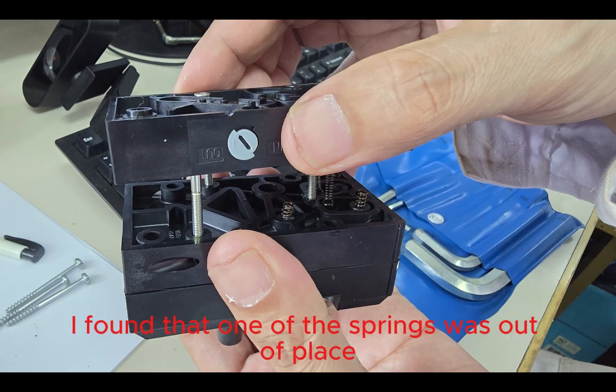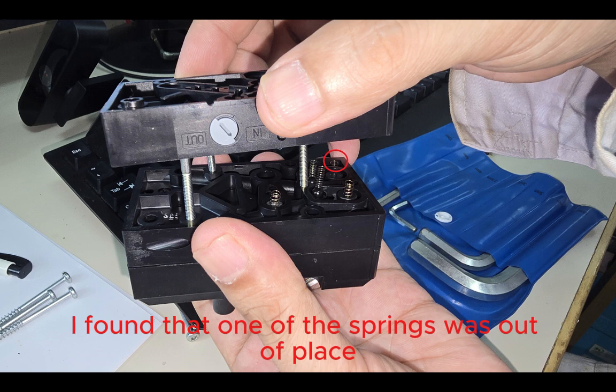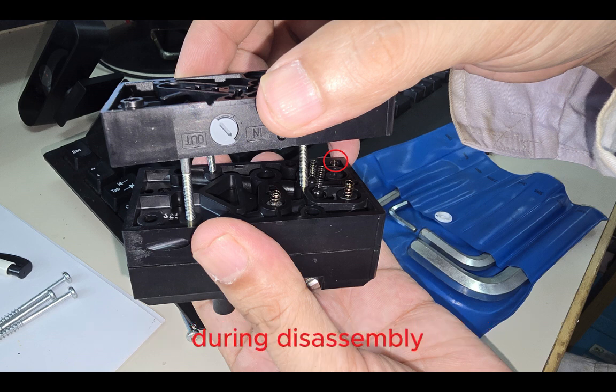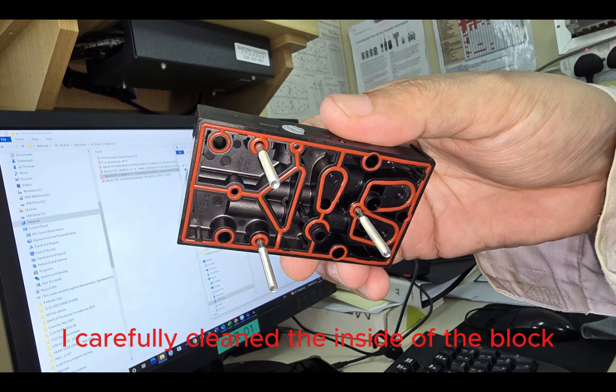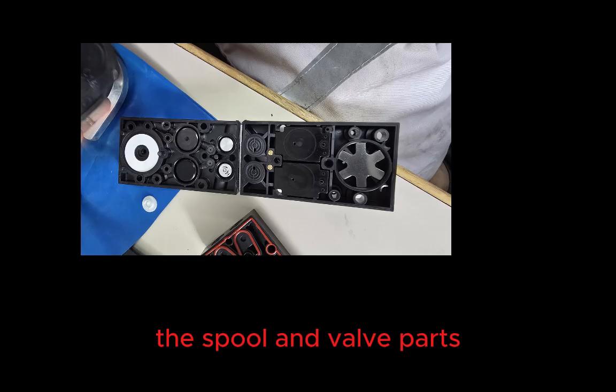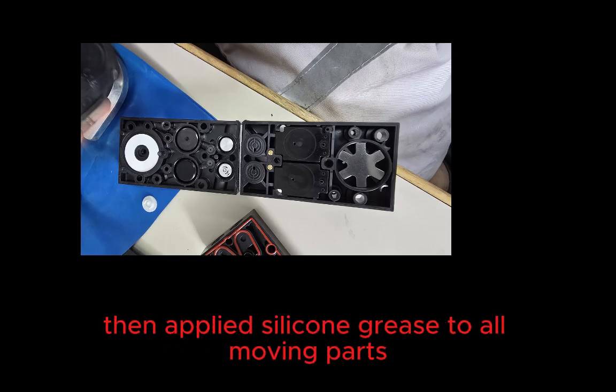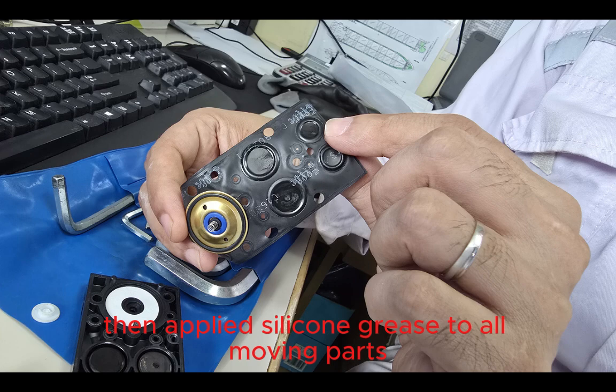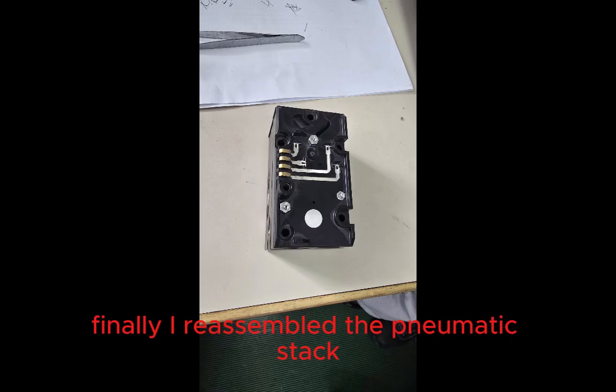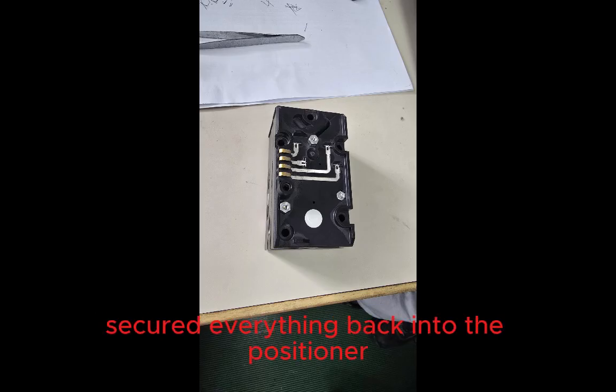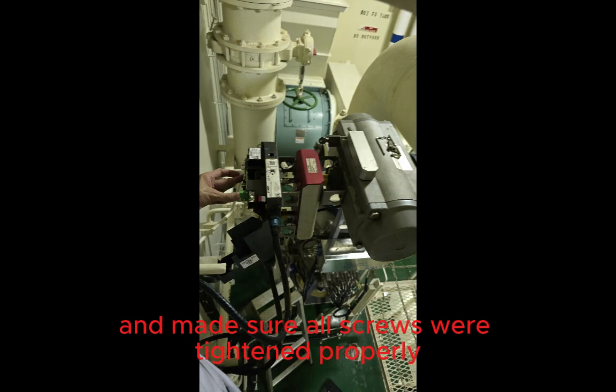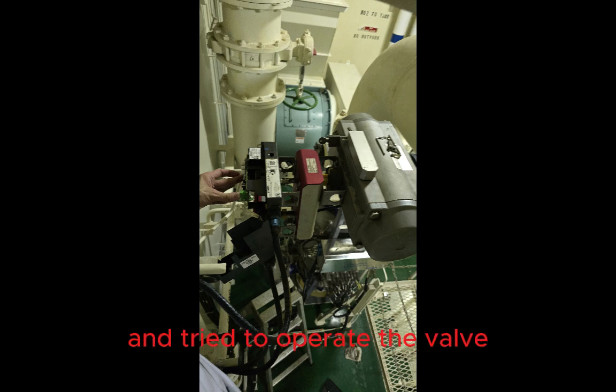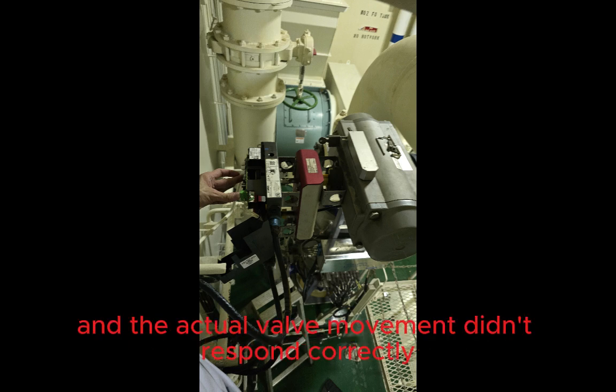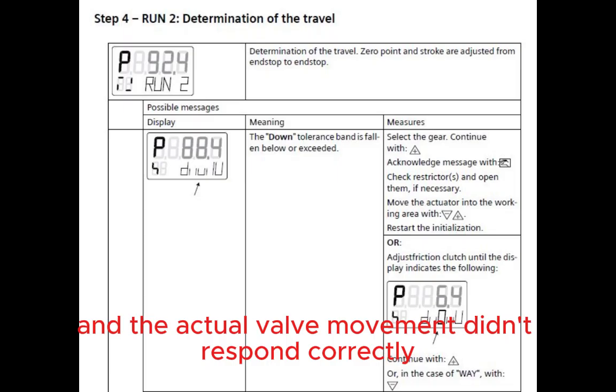Inside, I found that one of the springs was out of place, although I wasn't sure if it happened during disassembly. I carefully cleaned the inside of the block, the spool, and valve parts, then applied silicone grease to all moving parts. Finally, I reassembled the pneumatic stack, secured everything back into the positioner, and made sure all screws were tightened properly. After I reassembled everything and tried to operate the valve, it did open, but the command and the actual valve movement didn't respond correctly.